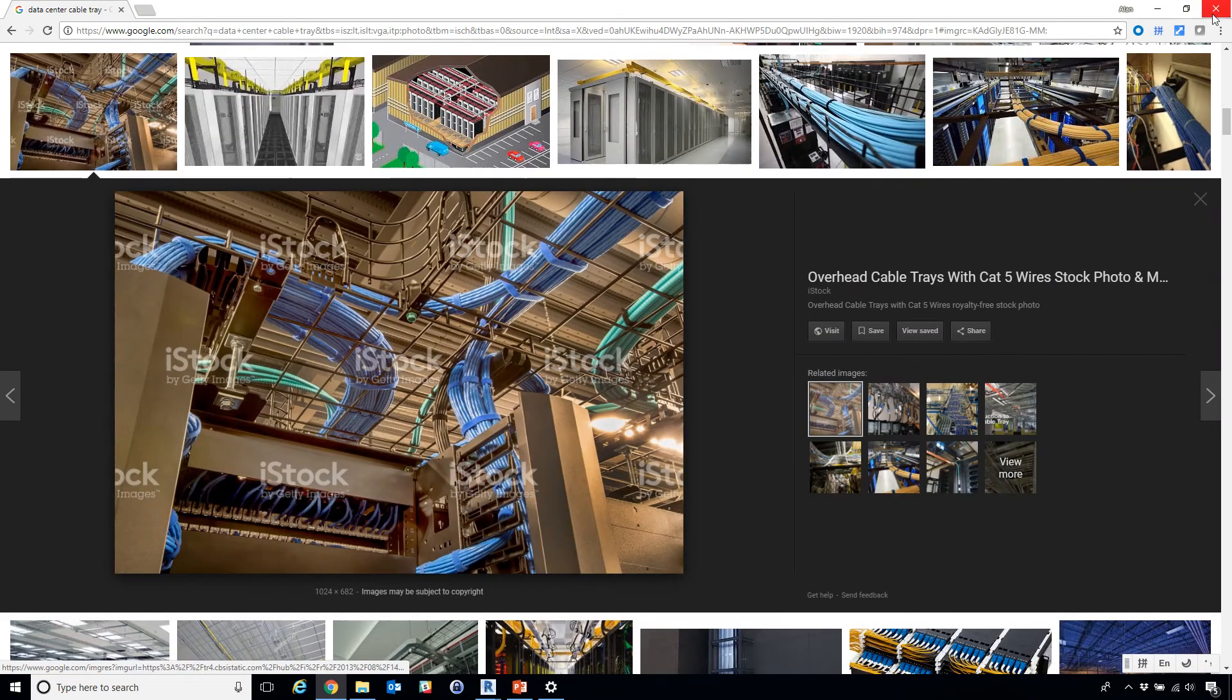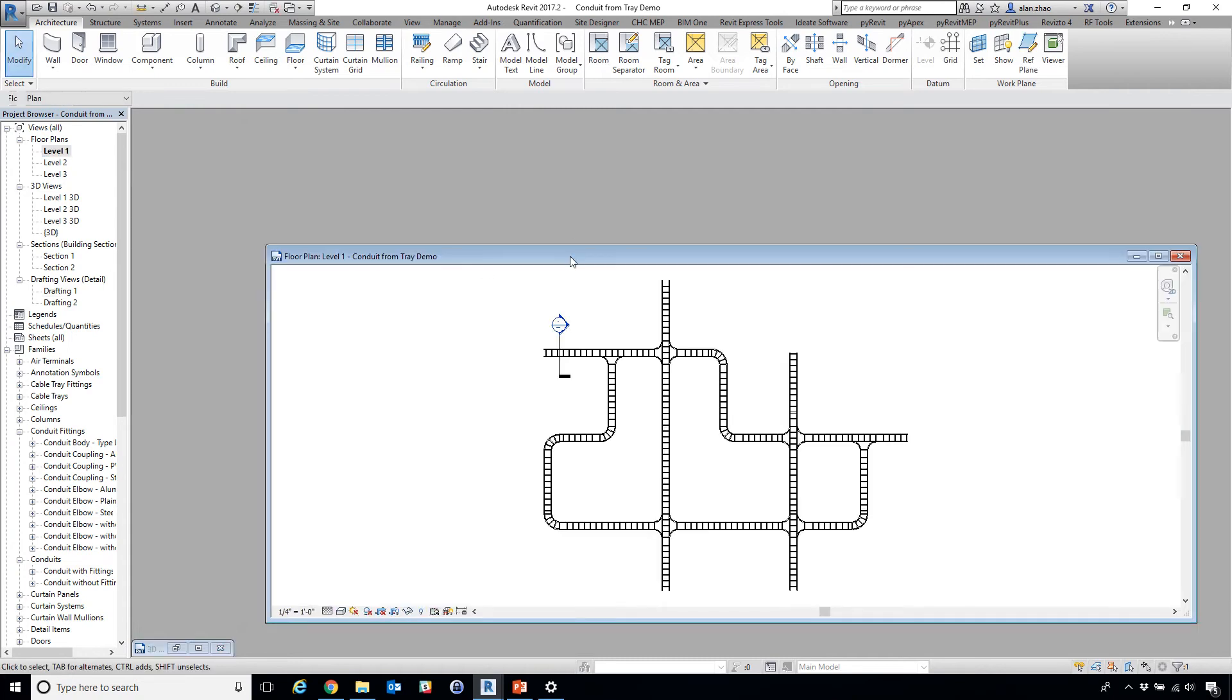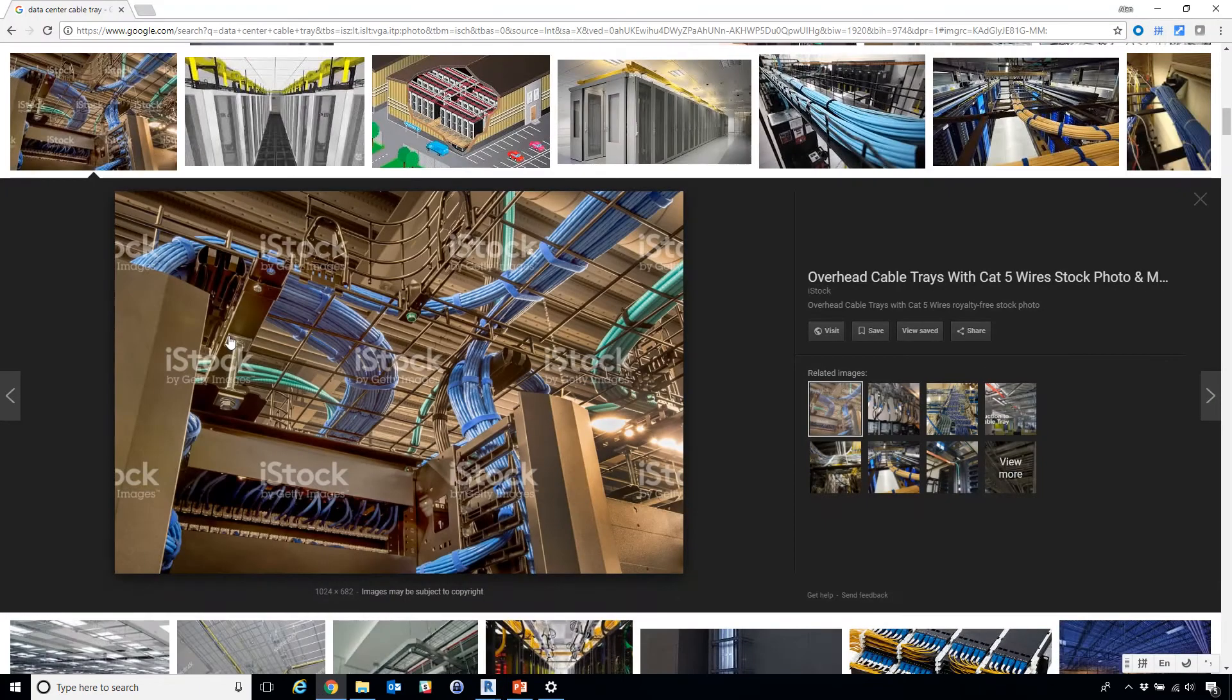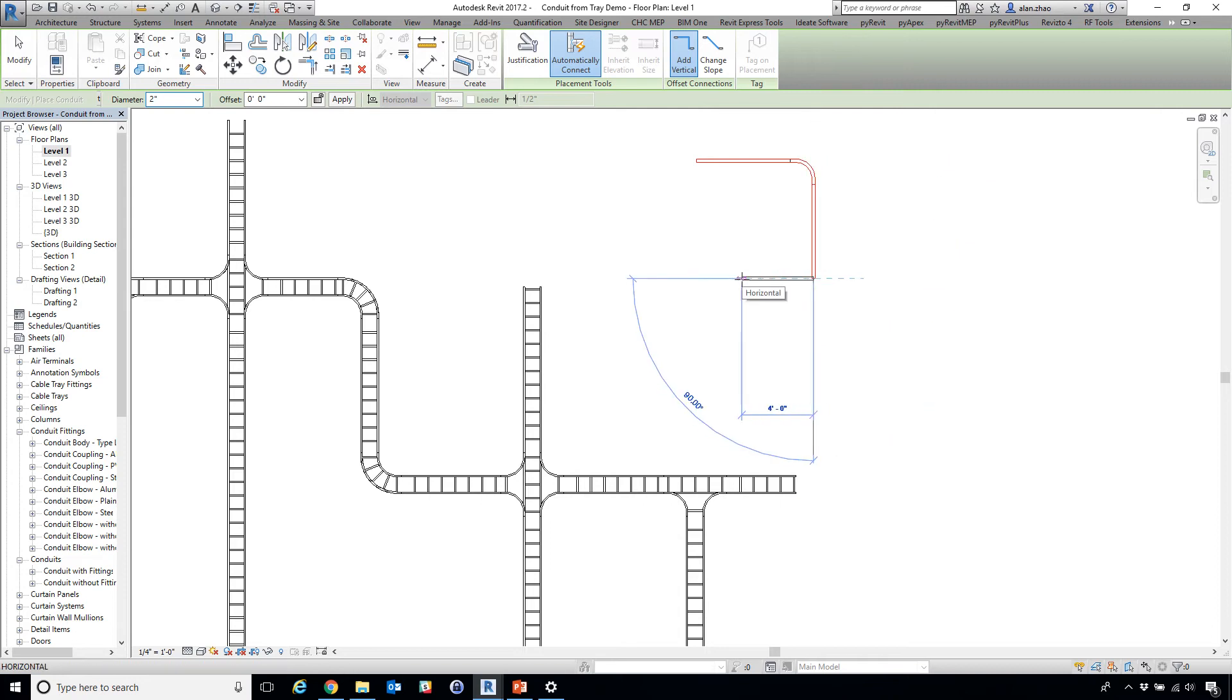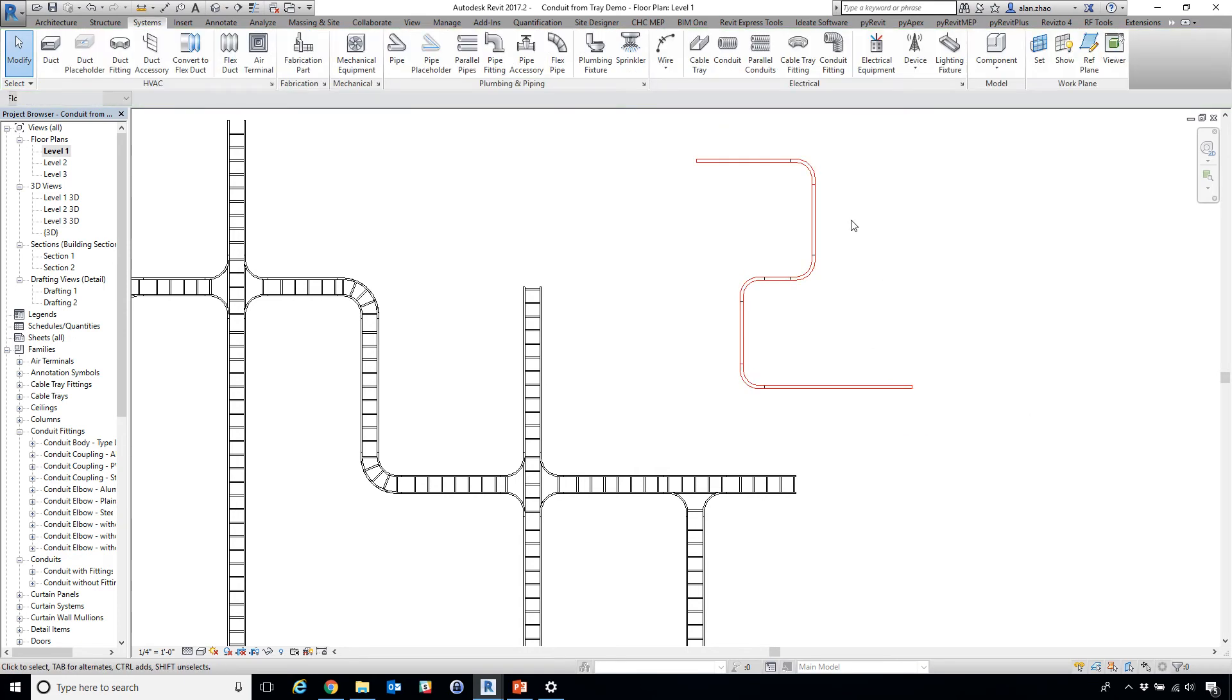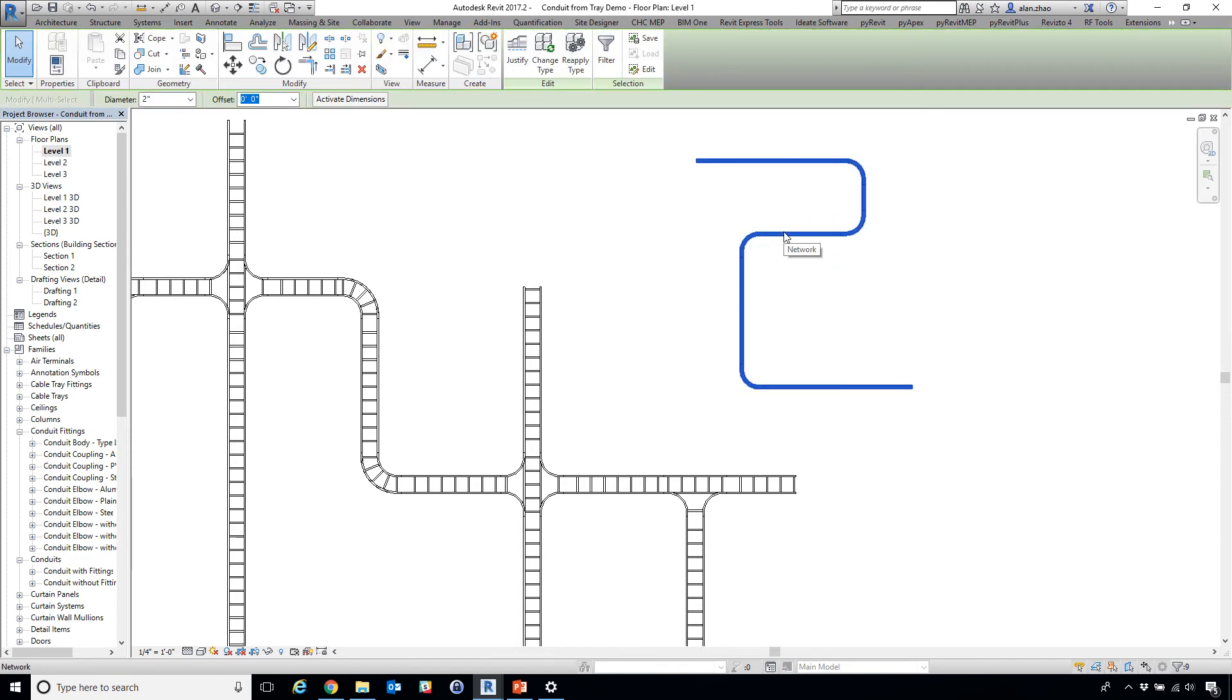So it is useful to model these in Revit as a way to visualize and coordinate. Here are rises and drops. The thing is, within Revit there is no default cable families. A way to work around is to model one of these bundles as a conduit. The benefit of conduit is of course it is a system family that allows the auto creation of fittings and you understand it as a complete run. So you can get the length and also you can drag and drop to make certain modifications.